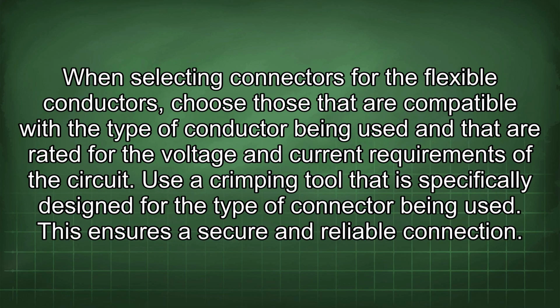When selecting connectors for the flexible conductors, choose those that are compatible with the type of conductor being used and that are rated for the voltage and current requirements of the circuit. Use a crimping tool that is specifically designed for the type of connector being used. This ensures a secure and reliable connection.